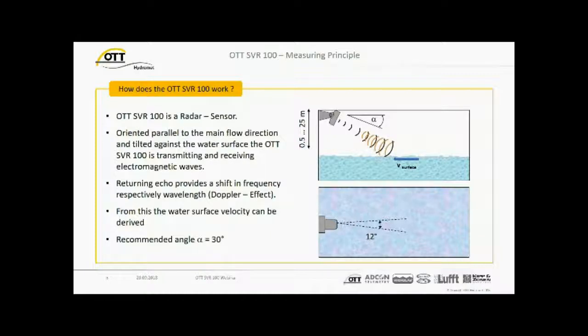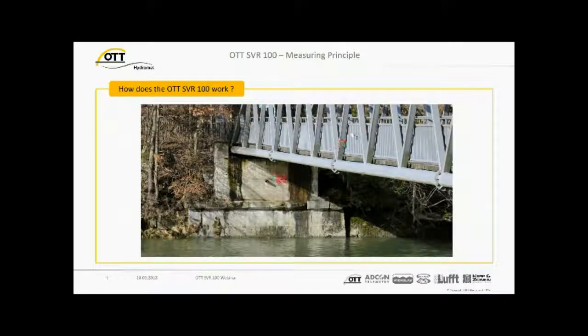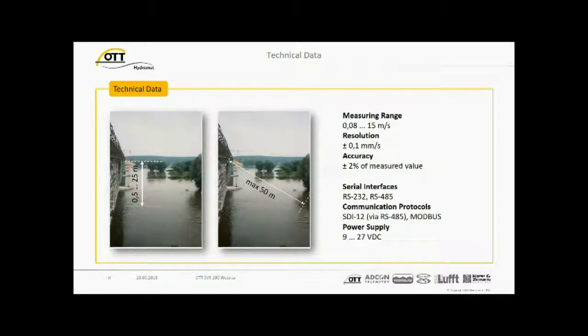A lot of you will know this from acoustic instruments, ADCPs, and so on. They also use the Doppler effect with acoustic transducers. From this, the velocity of the water surface can then be derived. And this is the easiest principle. You see, look to the water surface, transmit and receive electromagnetic waves, and take the Doppler shift and get the velocity from it. Same here, you can mount it on a bridge somewhere. Then you will have a footprint on the water surface because the area is an elliptical area where you get the reflections from. Depending on the height of the sensor and the distance, the area will change in size, of course.